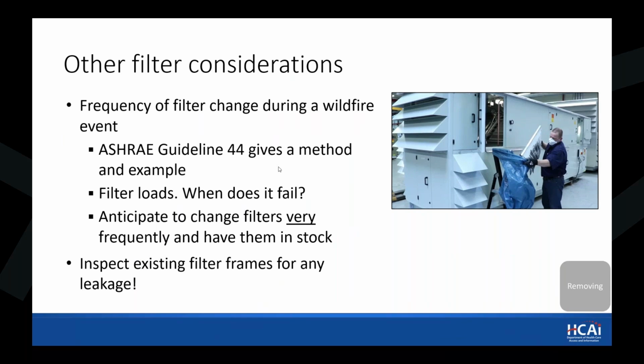And sometimes the question is always, well, can a filter fail? And yes, it does. It cannot keep holding dust in an unlimited way. Each filter has what we call dust holding capacity by weight. So once that weight is reached, usually by wildfire smoke, PM 2.5 or other particles, the filter and the frame are not designed to handle that much weight. It would just crumble down.